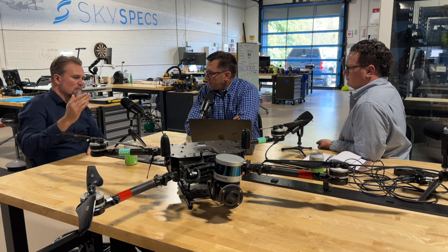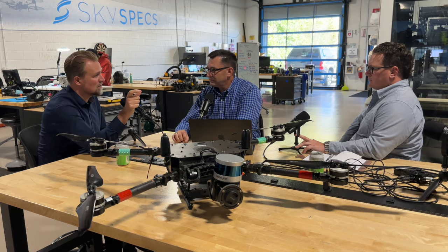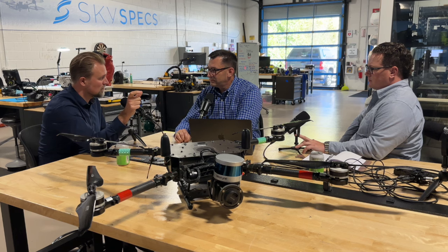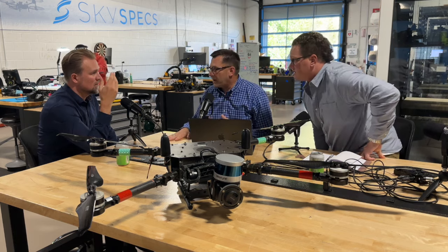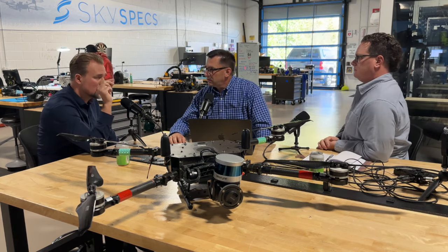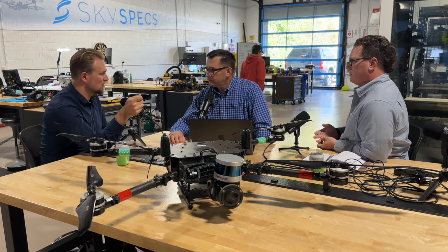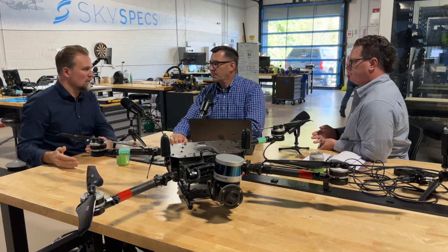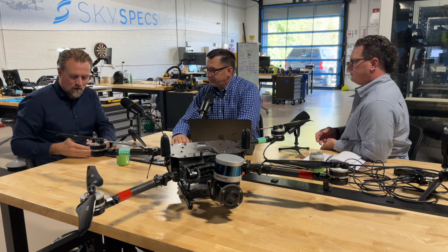For some often occurring failure modes, for certain populations of turbines, you'll have a big enough data set to say something. That's hugely valuable. But it's very rare that one actor has all of that data all at once, other than the OEM. And even when they have it, there's huge mechanical variance, even if you look at Siemens 2.3s, for example. Oh, sure. It's a very popular turbine. Because of different kinds of bearings in them, different blade sizes, different gearboxes. And even those bearings, even if they have the same model, have used different batches of metal, right? That's often how you find serial defects, right? That this or that batch of gearboxes was produced with a poor quality metal or tempering, right? So even within the same model, there are batches.